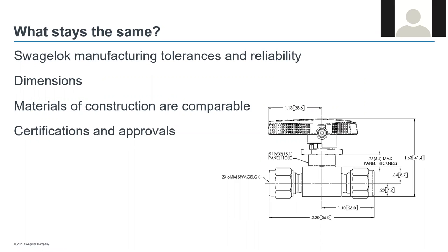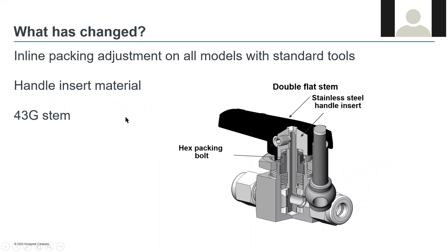On the 40G series, what has stayed the same? The Swagelok manufacturing tolerances and reliability remain the same. The 40G has the same external dimensions as the comparable 40 series models, ensuring a drop-in replacement. Materials are very comparable to the 40 series, with one difference being the packing material, which improves performance and temperature range. The 40G possesses the same certifications and approvals as the 40 series. What has changed: inline packing adjustments can now be made with common tools; the handle insert changed from brass to stainless steel, improving corrosion resistance and durability; and the stem changed to a double flat design, improving handle connection durability and ensuring proper field assembly.